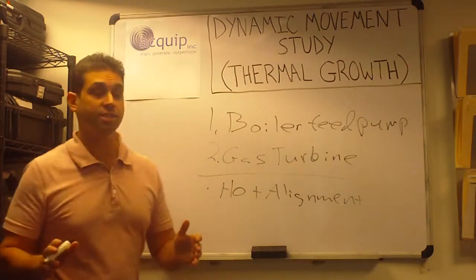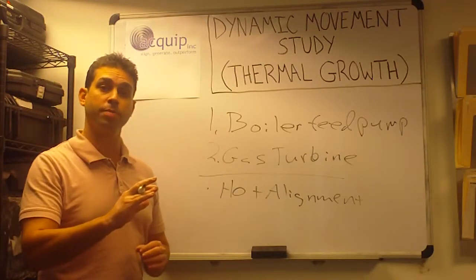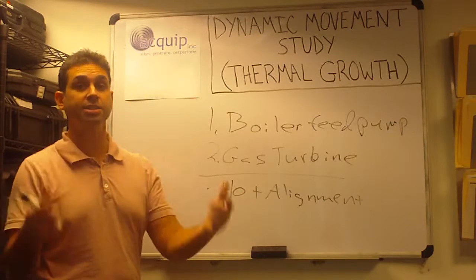What a hot alignment check is, is we'll shut the machine down, put all of our alignment equipment on as quickly as possible after we lock out and tag out the machine, and take a set of readings.